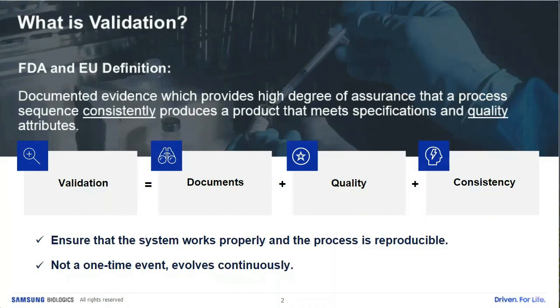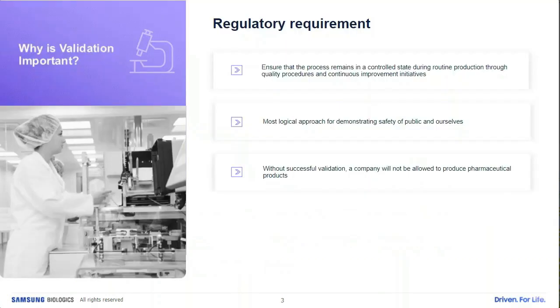This is not a one-time event when we talk about validation. It's always continuous, continuing through the life cycle of the facilities and equipment. It's a regulatory requirement, and validation is important. Most regulatory agencies, when they do a pre-approval inspection, come onto a site and look at whether you've done validation on your equipment and your processes. Without a successful validation, a company will not be allowed to produce pharmaceutical products, so it is part of the GMP guidelines.